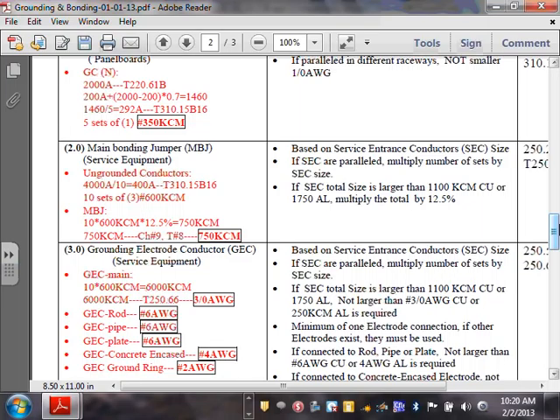But here's what you need to mess with though, the conduits. The manufacturers don't give you a copper bus bar to tie to the conduits, do they? They don't give you that. So basically, the main bonding jumper is done for you by the manufacturer. You might have to, if it's a grounded system, install it or remove it.